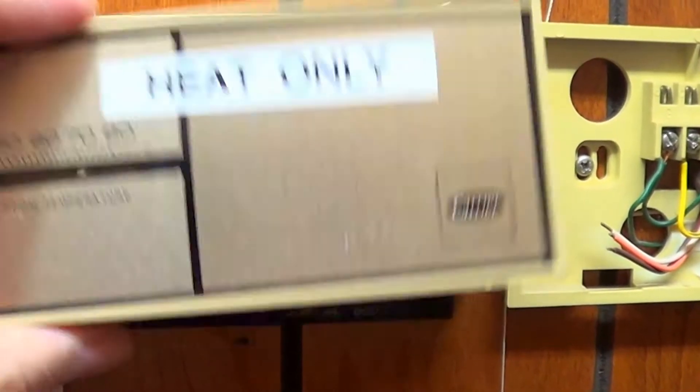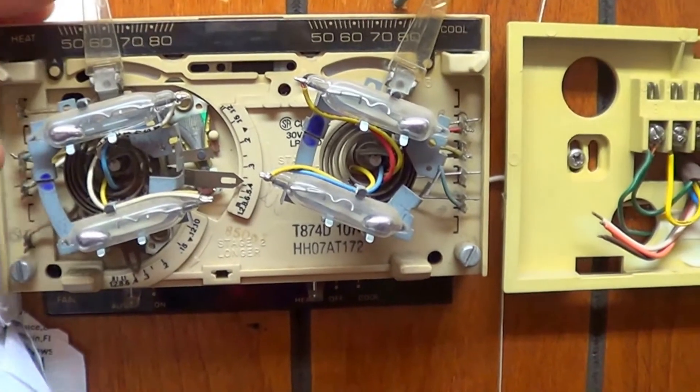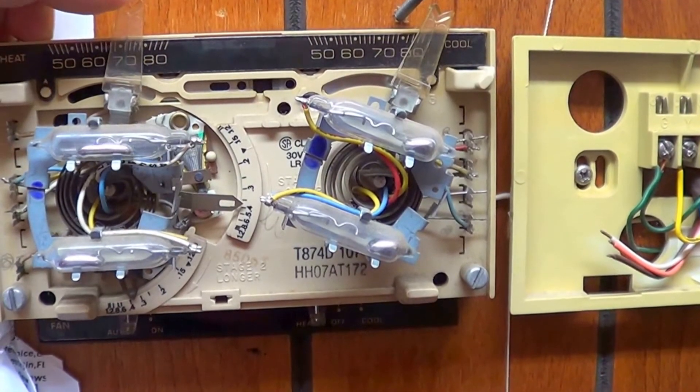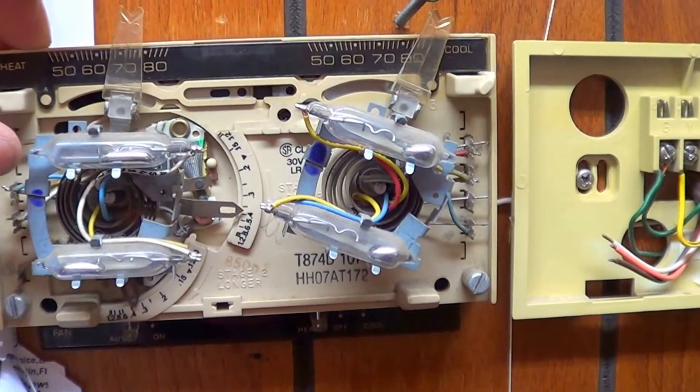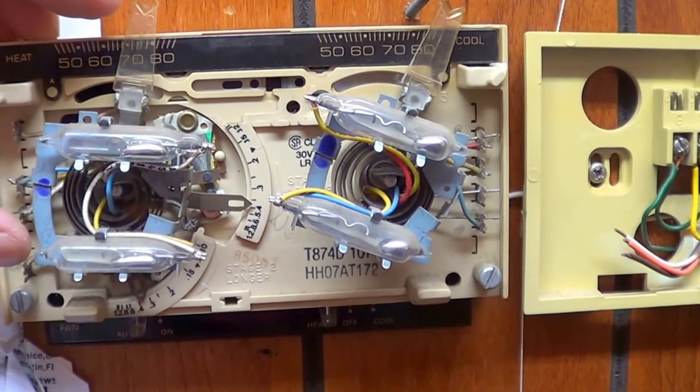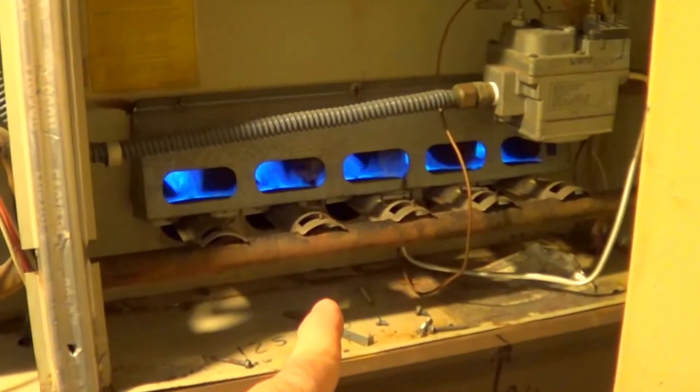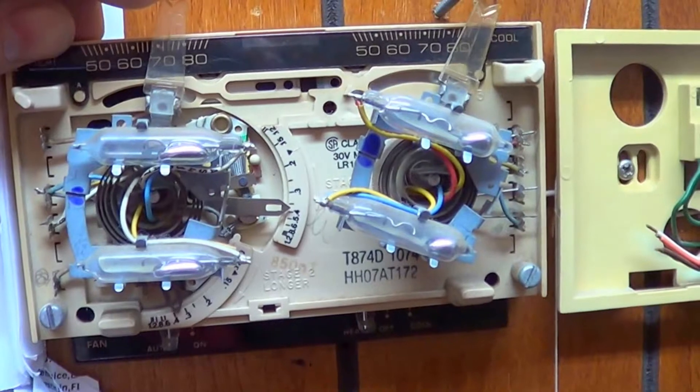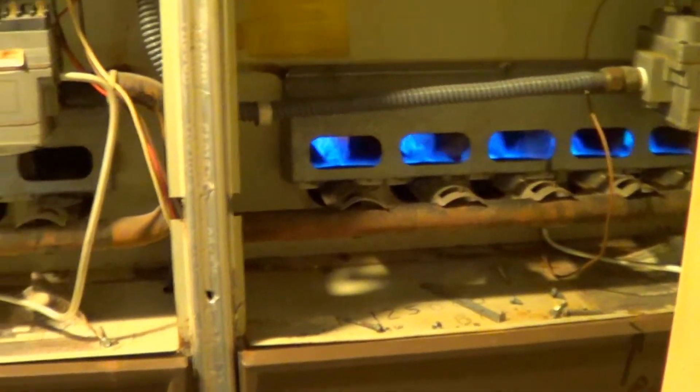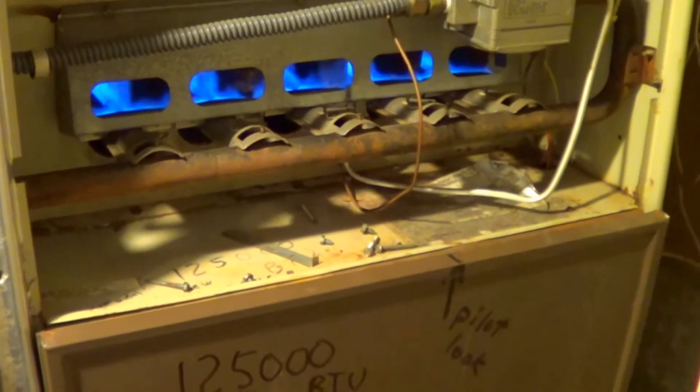In summary, here's the twinned thermostat. Take the cover off real quick. These are the two mercury vials. If I move this up the call for heat, that turns on the first furnace, which is the right one. It commands the gas on with the big delta T, it kicks the left one on. I'll go over real quick. Got the left furnace on, I've got the right furnace on. Go back over here real quick and turn that down. Now it's only running on one furnace, which is the right furnace.